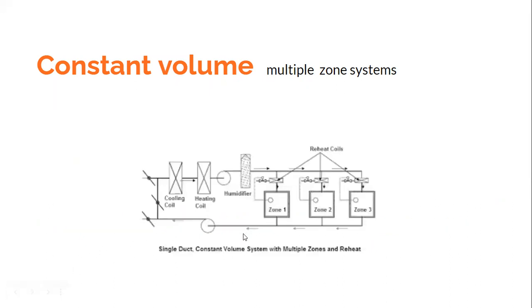So this schematic would explain the constant volume system with multiple zones. Look at this. This is a cooling coil. This is a heating coil. There is a humidifier. We are supplying this condition here, and a constant volume is being supplied to zone 1, zone 2, zone 3 via the reheat coils. And these reheat coils are basically controlling the zone 1, zone 2 and zone 3 temperatures. So these are very critical.